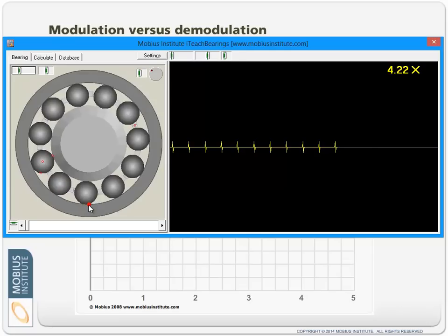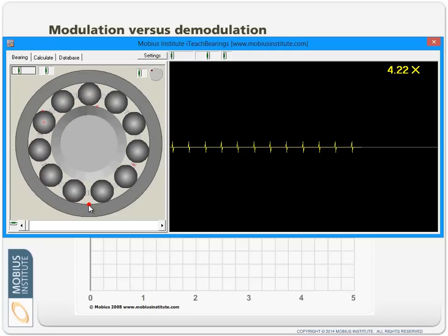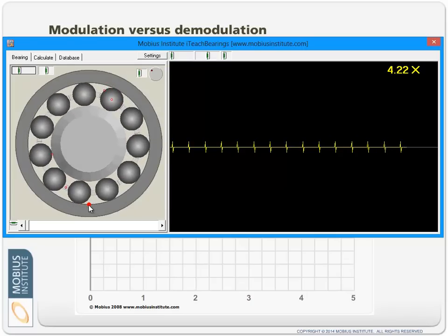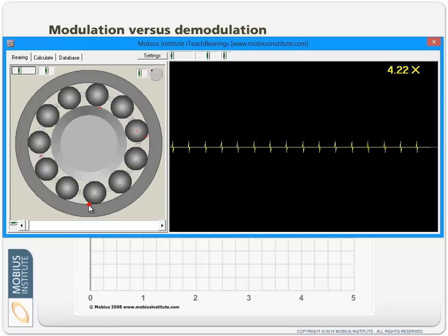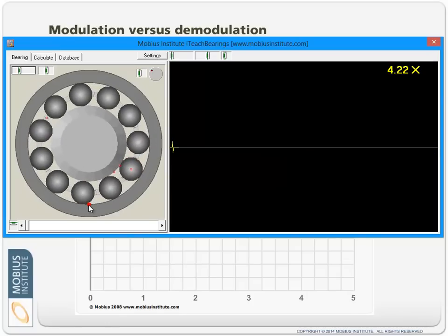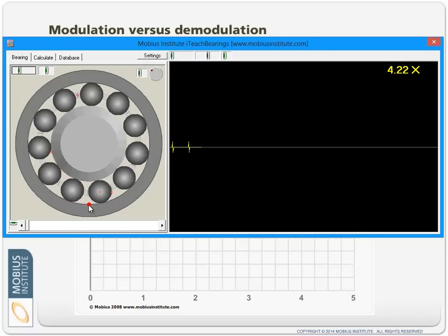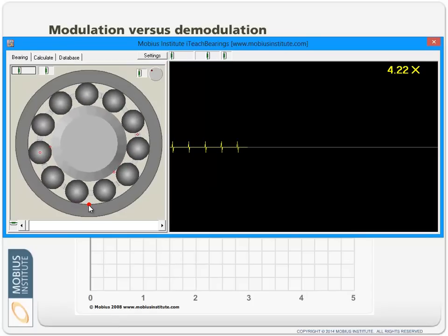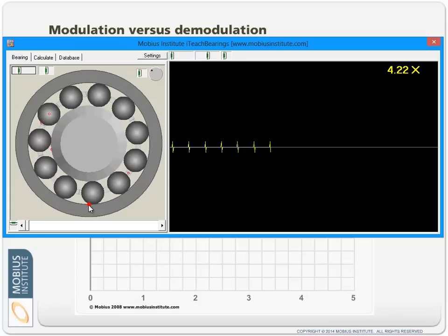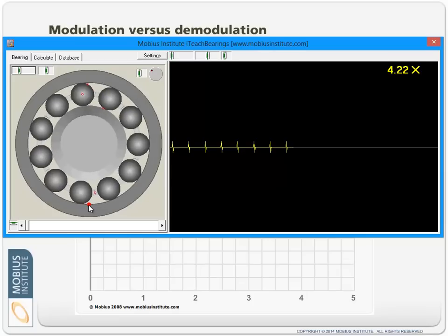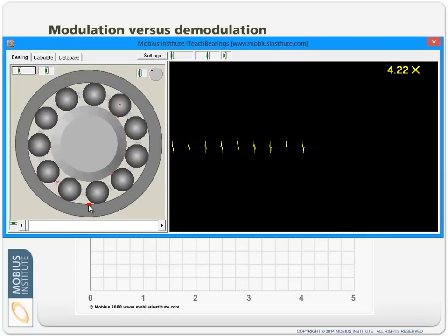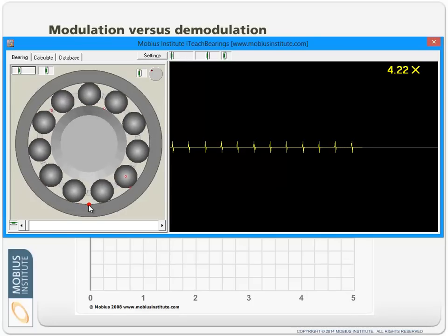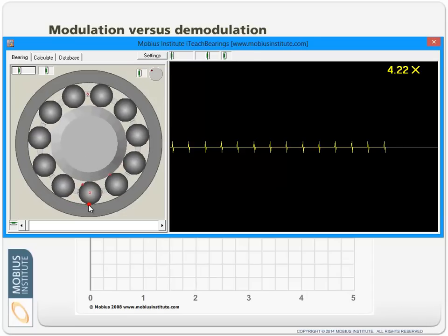But every time we get a ping, something else happens inside the machine. Any time you've got metal-to-metal contact, a stress wave goes whooshing through. Imagine a great big metal bell, and we've got this little metal clacker, whatever those things are called, and we just give the bell a little light tap. We may not hear the bell ring, we may not be able to hear the tap at all, but in actual fact, because of the metal-metal contact, we can detect the stress wave or the shock pulse that ripples through. If we hit it just a little bit harder, again, with all the other sound going on, imagine that this bell is surrounded by all this traffic and a lot of confusing noise at lower frequencies. We couldn't possibly hear a person just tapping that bell.